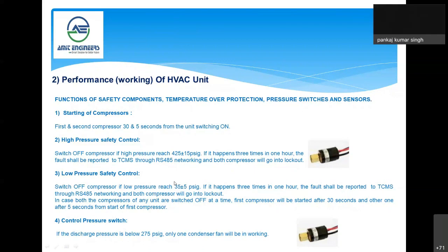Similarly, there is a low pressure safety switch. Again, if the pressure goes less than 35 plus or minus 5 psig, there will be a signal given to the TCMS. This is a control pressure switch to switch on and off one fan based on the pressure. This pressure is directly proportional to the temperature.